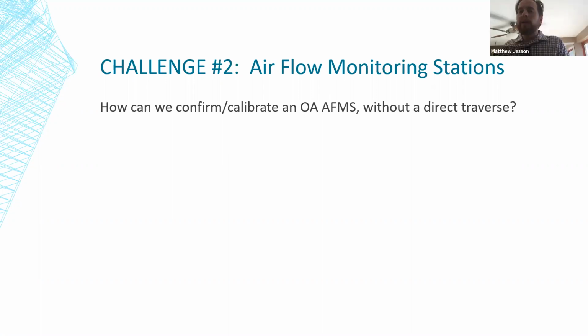Okay, gotcha. I think I understand what's being asked, and I believe that might be answered in the next slide here, hopefully. So when we talk about calibrating airflow stations, that might be kind of a bad word to use with the airflow station manufacturers. They are factory calibrated typically. And what their literature will say is that they need to be confirmed, validated, et cetera, by the TAB technician in the field. So we tend to refer to it as calibrating, because typically we will take a measurement, compare it to the airflow station reading, and adjust a gain factor or some sort of correction factor to obtain a similar reading on the airflow station. If it's very close, we just leave it as is.